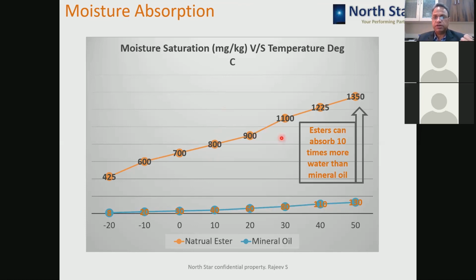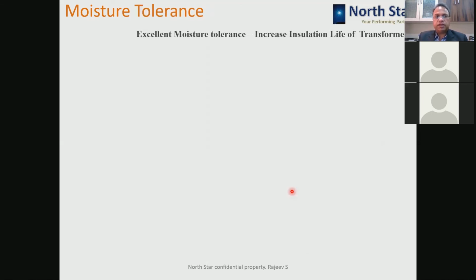So since water is getting absorbed, it is not causing any damage to the winding or insulation, and it is not available freely inside the transformer. So it cannot cause any problem in the metallic components like terminals or OLTC contacts or other such parts. So because of this, your transformer is quite strong against the attack and effect of moisture. Okay. Second is moisture tolerance. Further, we are taking this topic to a deeper level. What is moisture tolerance? It means the property of a material of sustaining or maintaining its insulating properties as good as a new material, even when the moisture is more inside it. So it is more tolerant towards the ill effects of moisture.